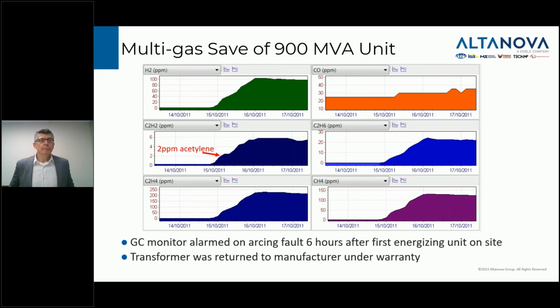Okay, another good case study I like to present relates to a GC monitor we deployed on a new transformer — a brand new 900 MVA unit somewhere in the southern US a number of years ago. The owner installed the DGA monitor a few days before they first energized this new unit on the pad at the site, so they had a bit of a baseline. When they switched on the transformer and first energized it, what they saw was dramatic.